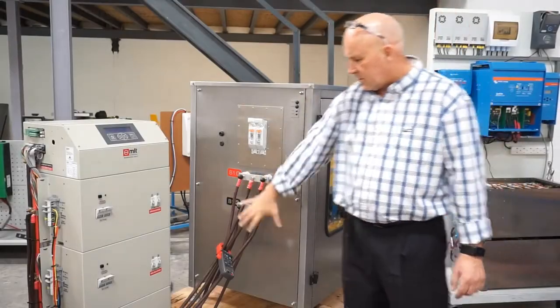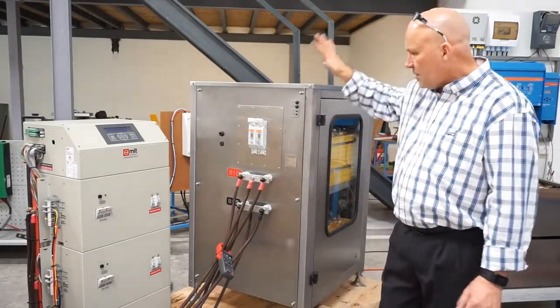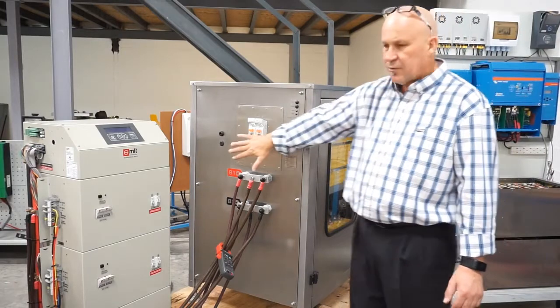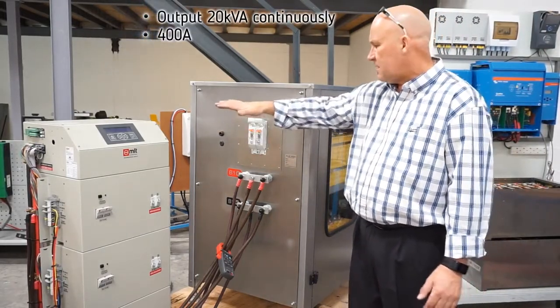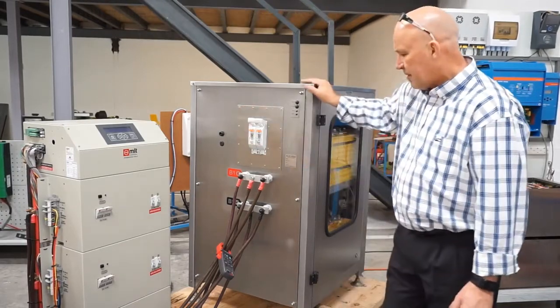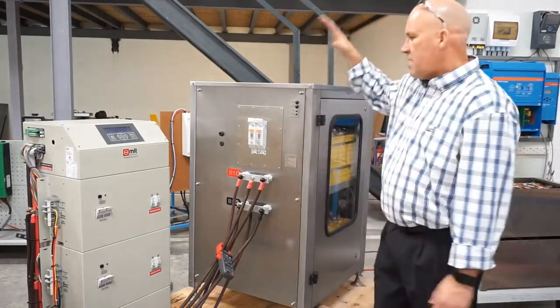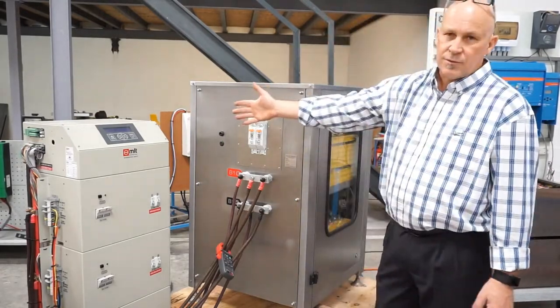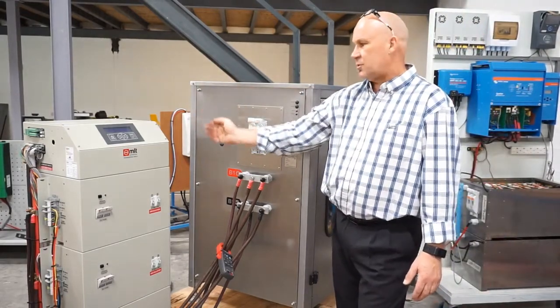We've connected the batteries to the busbar, so this little busbar adapter. This specific battery has been configured to deliver 20kW continuously, and that means it's rated for 400A, so we'll take it up to 400A just now. We've got a current clamp to monitor the DC voltage, and I'll take you through a couple of the displays on the inverter to show the charge and discharge currents.